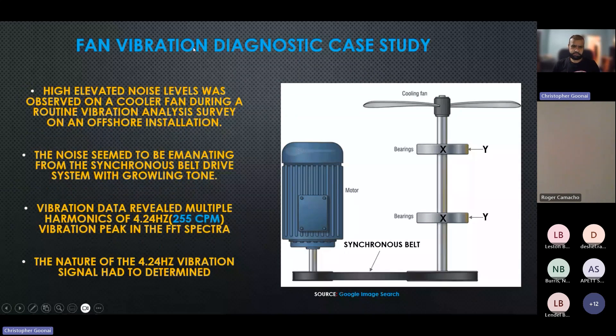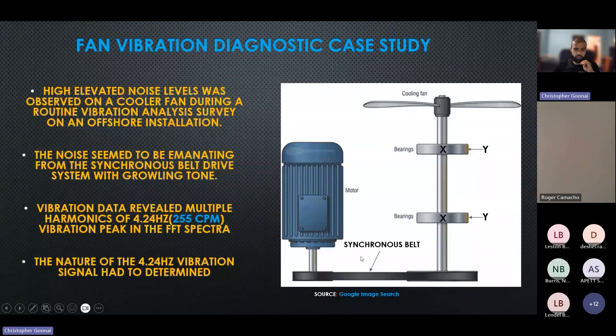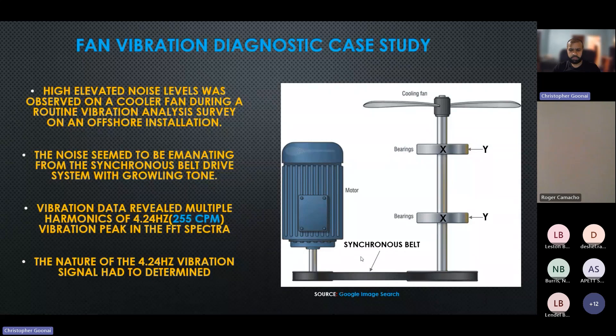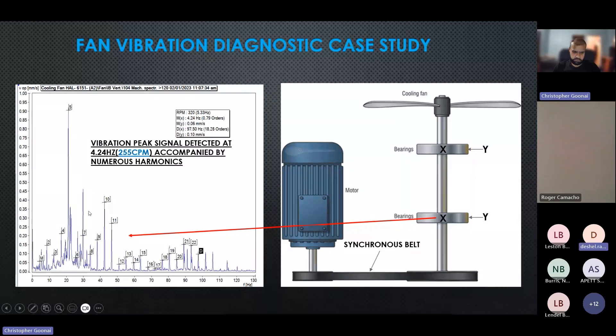Now the case study — the synchronous belt issue I encountered. High elevated noise levels were observed on a cooler fan during a routine vibration analysis survey on an offshore installation. The noise seemed to be emanating from the belt drive region — I heard a growling tone and somewhat of a high-pitch tone. I assumed it was the belt, but let the data guide me. Vibration data revealed multiple harmonics of 4.24 Hz — that is 255 CPM — in the FFT spectra. The nature of that 4.24 Hz vibration signal had to be determined; if I could prove that was the belt rate, then I could prove it was a belt defect.